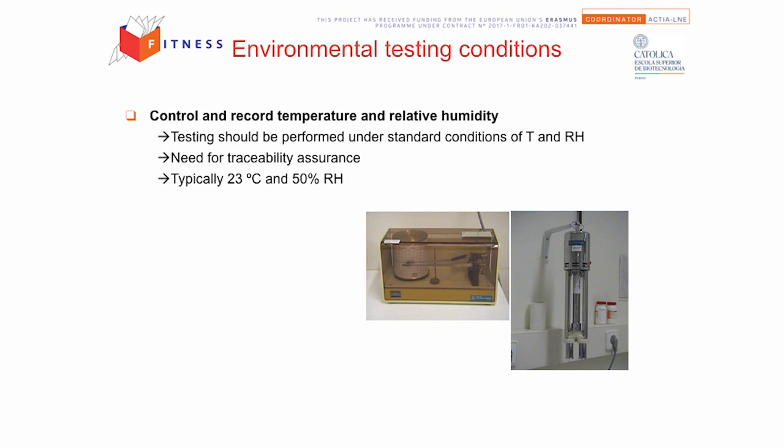And our laboratories use this type of equipment that you probably know. We have two thermometers, one dry and the other one wet. And this is the most precise method to measure the temperature and the relative humidity. And then we have a continuous record that can be more or less advanced. But it's important to keep the record of the conditions during the tests.